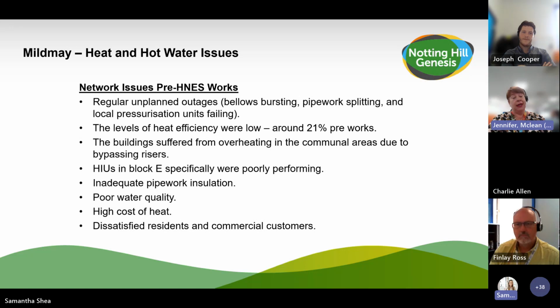Also, there was a block, Block E, called Appel Court, which was specifically poorly performing. We had inadequate pipework insulation that didn't meet current guidelines, and some of that insulation was actually missing across the network. The water quality was identified by Fairheat as a particular source of problematic functioning of the network, as well as a high cost of heat due to all that bypassing and overheating.